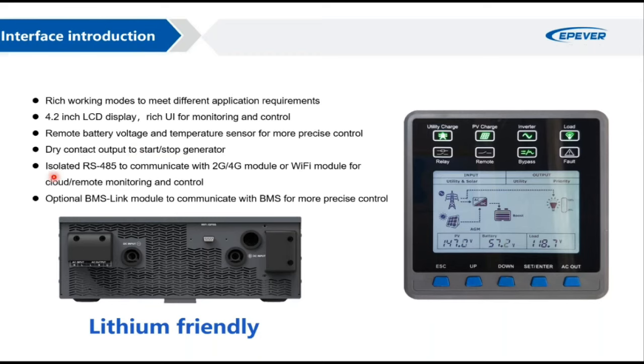Via Modbus RTU protocol, you can access all this information, and modules like a 4G module or Wi-Fi module provide remote access to those parameters or cloud access. This also works based on Modbus on an isolated port, so this communication port is actually protected and isolated. In general, you can monitor this device remotely or via cloud.